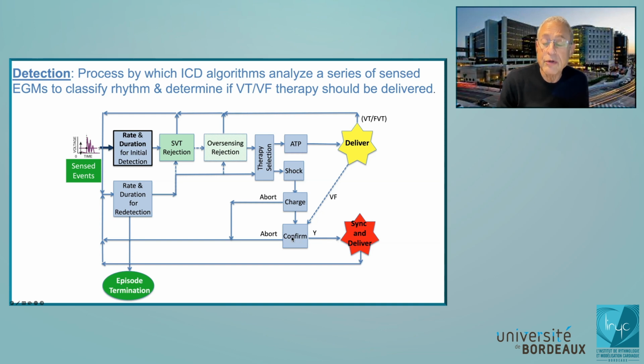Pierre, something new you will see with EV-ICD is that the anti-tachycardia pacing has to be delivered through much higher amplitude pulses than we typically use with standard pacing pulses in defibrillators. For that reason, the ATP is delivered actually through the shock capacitors. And you, for the first time, will actually see a delay in therapy delivery between detection and ATP. And you want to say, hey, what's going on in there? It's not a 10-second delay, but it takes a second or two to charge up the shock capacitors to enough voltage to deliver the sequence of ATP. So that's something, Pierre, you'll see differently in EV-ICD.